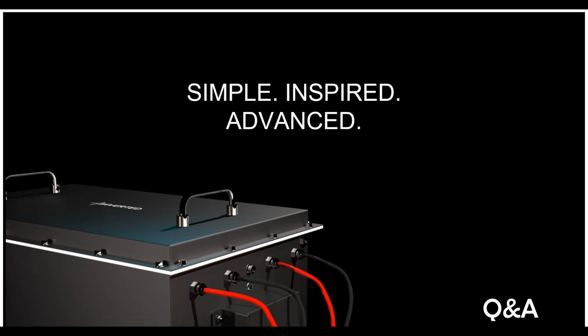Okay, so to add to this question, if my battery pack is 45 kilowatt hours, I have to consider the usable capacity to be around 90% for NMC, right? Correct, absolutely. So if your battery bank is 45 kilowatt hour and you're determining it at 90% depth of discharge, your usable capacity would be approximately 40 kilowatt hour, which is 40 units. So the OEM will be able to use only up to that level.